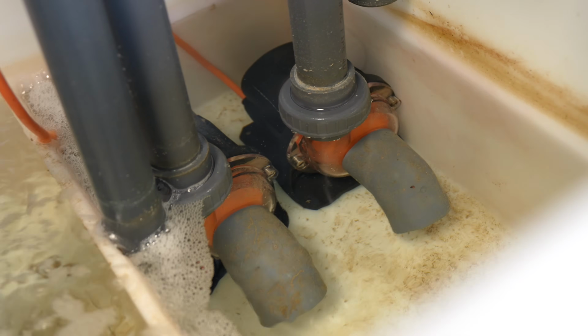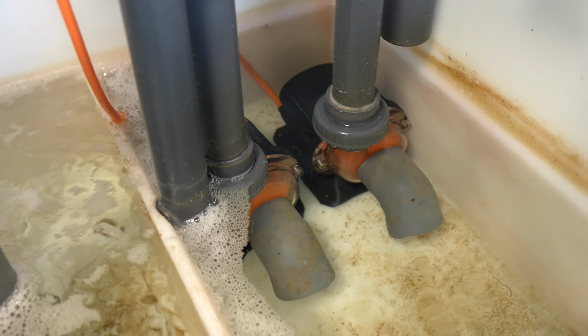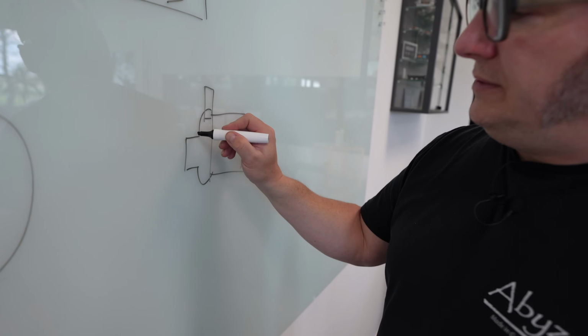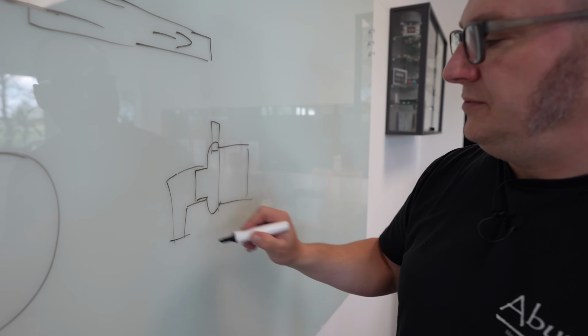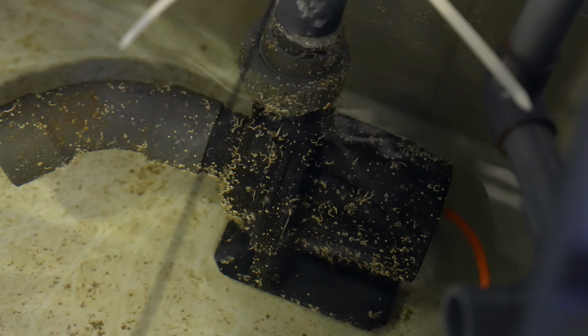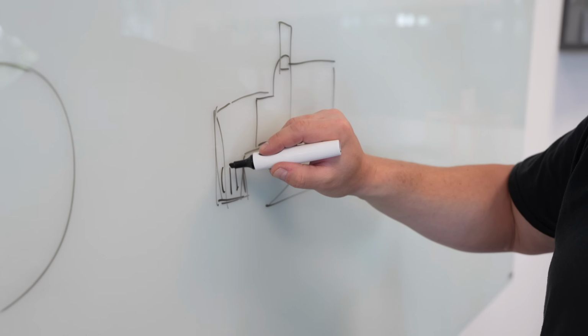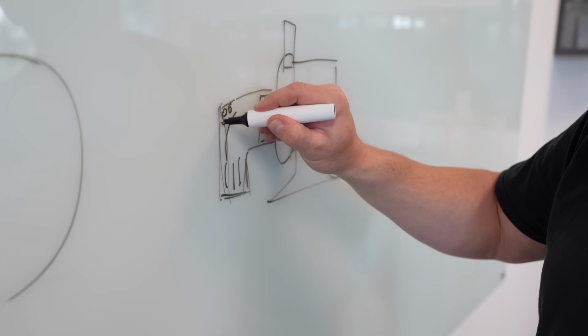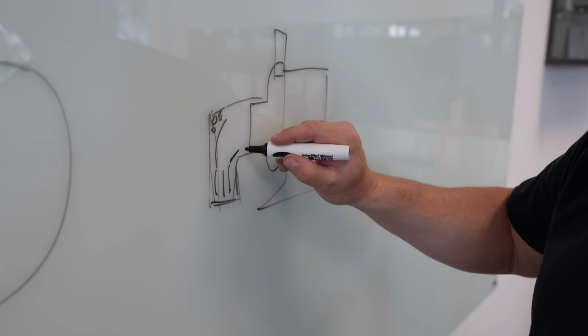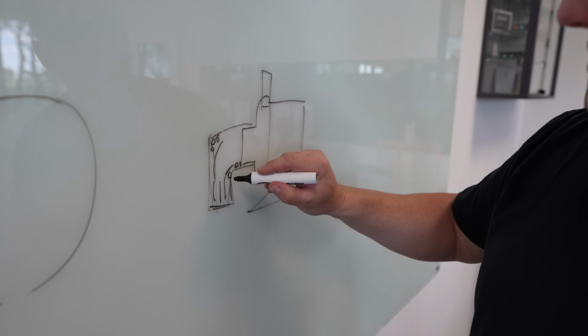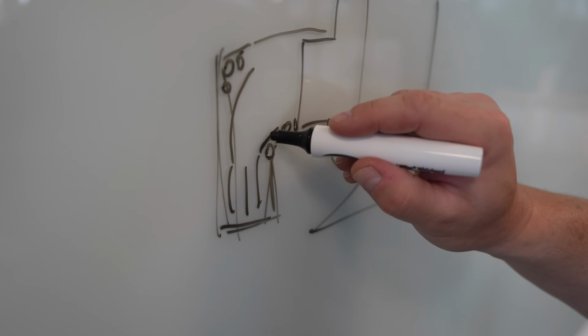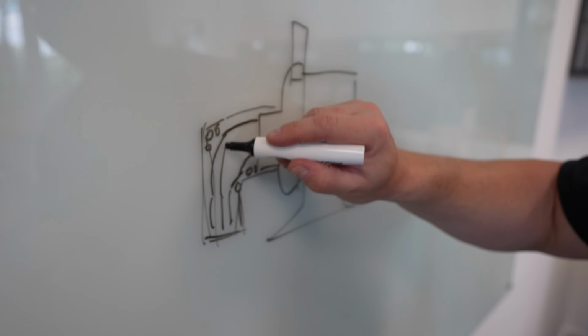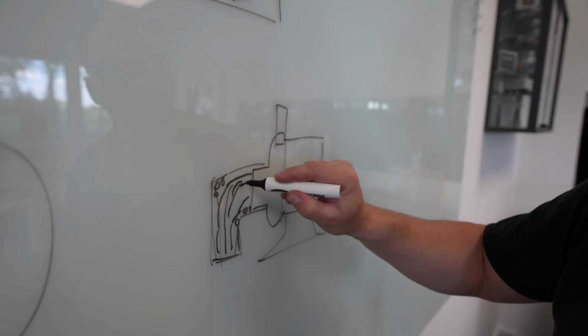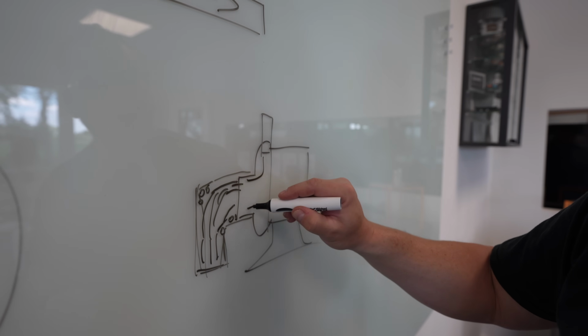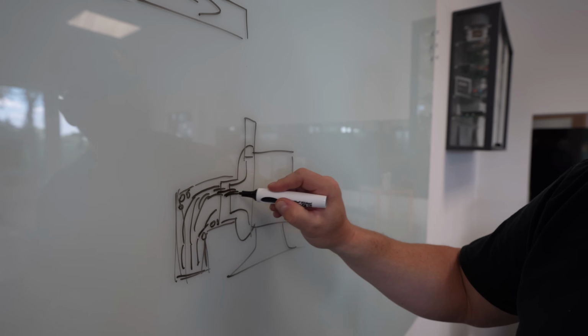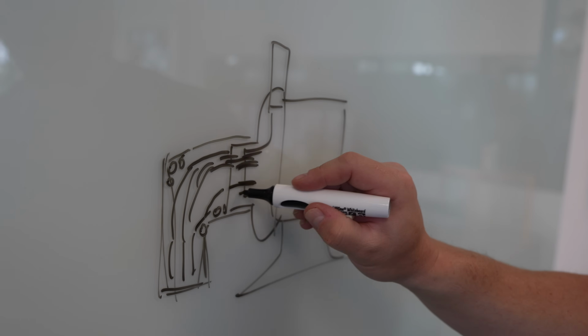There's also something else to consider when mounting with an angle in front of the pump, and I will show you because I have that in my tank. So we have our pump head here, that's the pump, here's the outlet. If you mount a 90-degree angle in front of the pump, or if you have your plumbing going in with a 90-degree elbow, the water comes in here. On this corner you will have micro turbulences, and around this corner you will have micro turbulences, and here you will have micro turbulences. So you're actually pressing the water, due to the centripetal force, to the outside of this elbow. So what happens on the inside of the pump, here's your impeller wheel, is that you're pushing more water pressure on the top and less on the bottom.